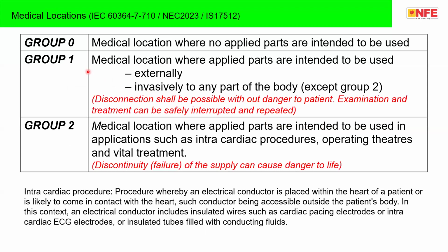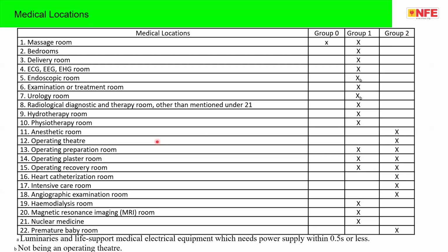On the other part, the location: medical locations are classified into group 0, group 1 and group 2 medical locations. Group 0 is a general area where no treatments happen. Group 1 is a location in which the applied parts are used external to the body of a patient. Group 2 is a medical location where applied parts are used internal, that means inside the body of the patient. So the groupings are very critical. And the National Electrical Code has this kind of a table. You can find the different types of medical locations, the classification of each medical location, and the recommended grouping of rooms.